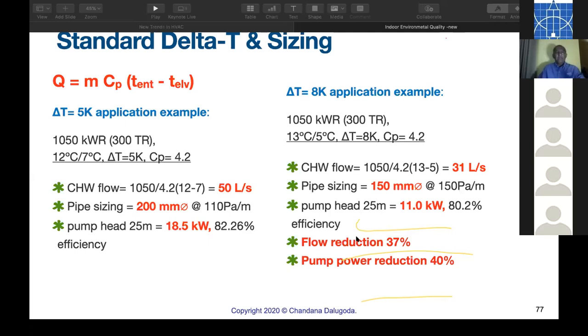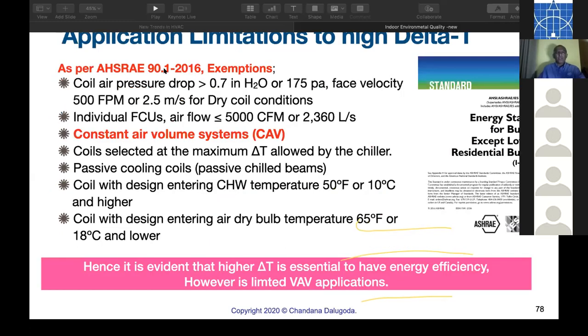What are the limitations? ASHRAE 90.1 2016 comes with exceptions. Coil air pressure drop 175 Pascal or higher. Face velocity should be 2.5 meters per second. For dry coil conditions are exempted. For dry coils, sensible coils, no. Individual fan coil units below 5,000 CFM, this high delta T is not required.